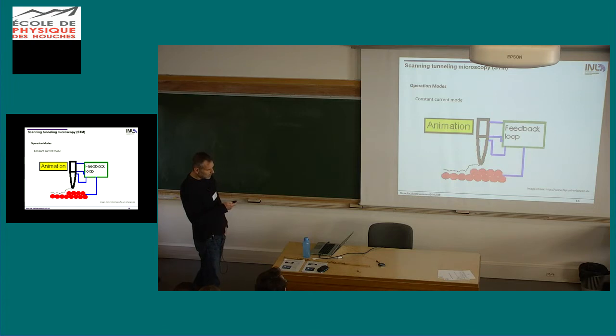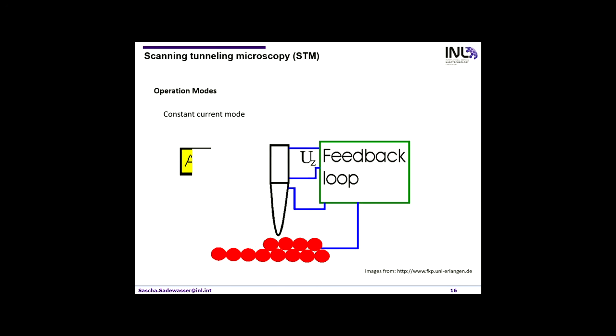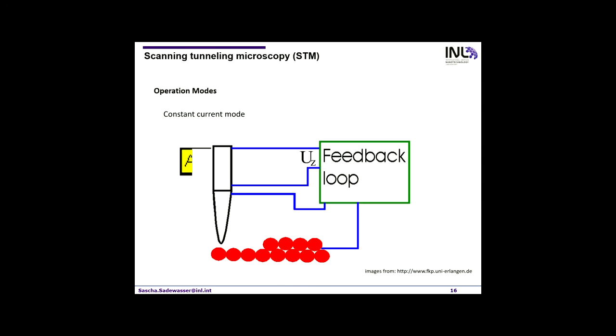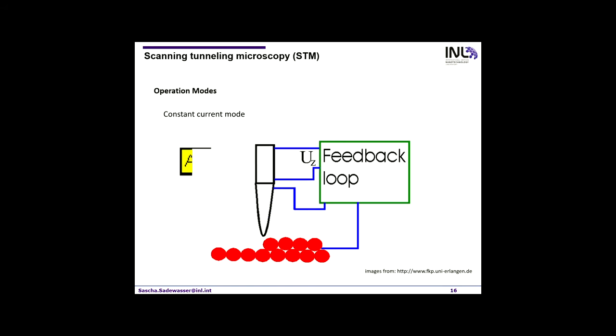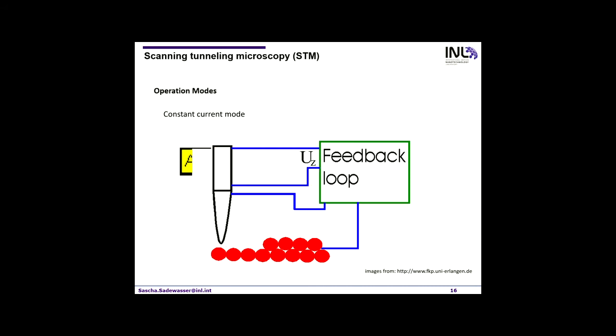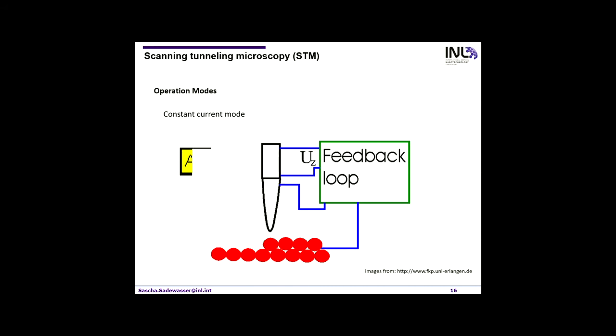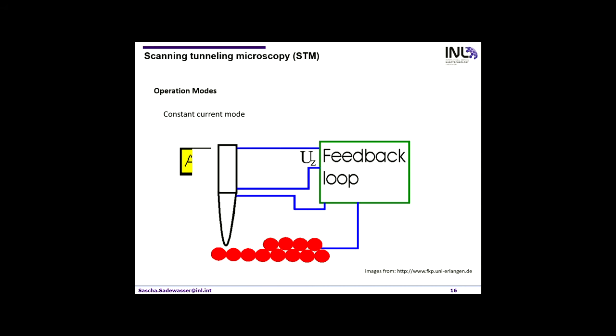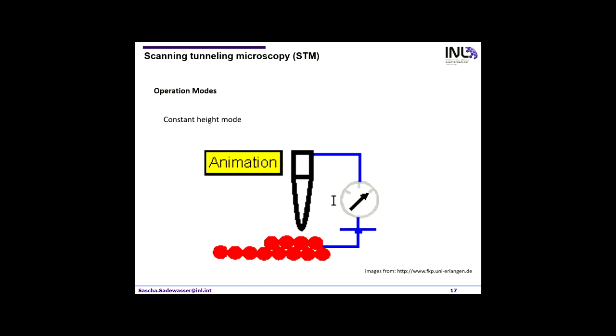And this we had already. So there are different operation modes. One possible way to apply this is the constant current mode. I said this essentially already. Here you just always keep the tip at the distance where it gives the same current, some nanoamps or whatever. And then you do a feedback loop to apply the Z voltage to the Z piezo, so that the tip is maintained constant above the surface. So you essentially get a direct measurement of the surface topography if you have a calibration of your Z voltage. So that's a very simple and very common one. But it requires a feedback.